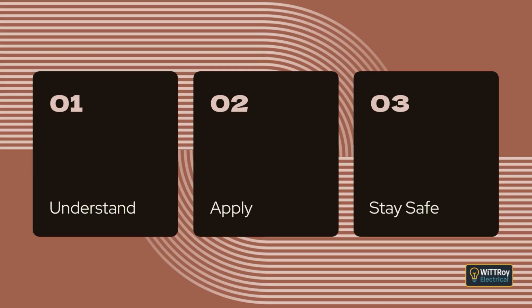Verification also includes checking that all conductors are connected correctly, especially to protective devices, switching devices and control devices. This ensures that fuses, circuit breakers, RCD devices and switches will operate as intended. Reference to Section 8. Section 1.8 tells you what must be done. Section 8 provides the detailed procedures and tests, essentially, how to do it. In simple terms, Section 1.8 says test it, and Section 8 says here is how you test it.